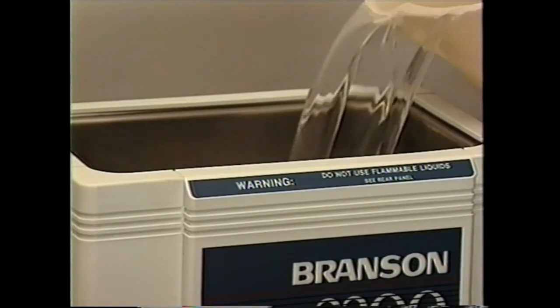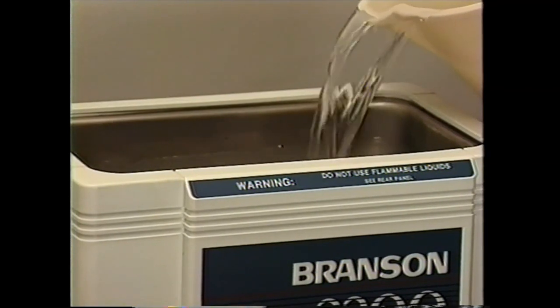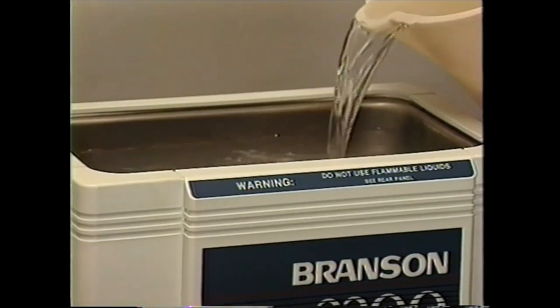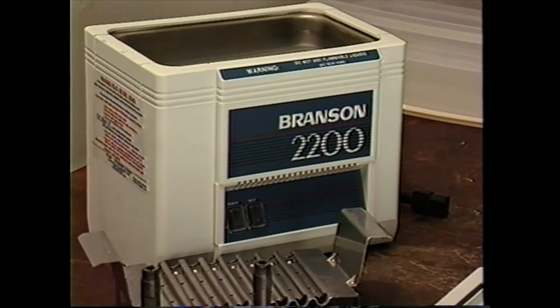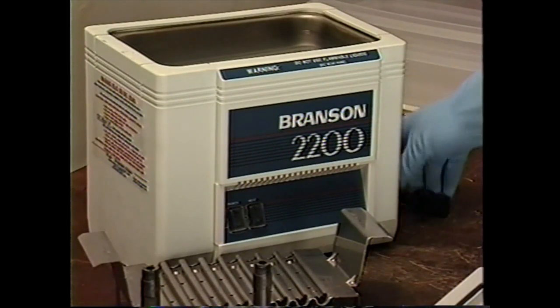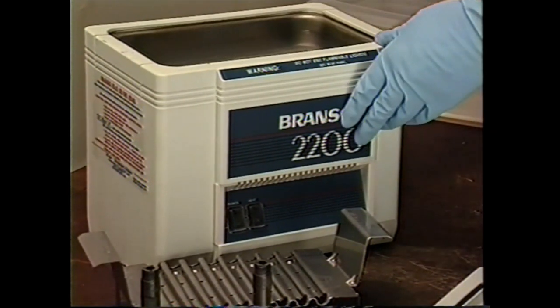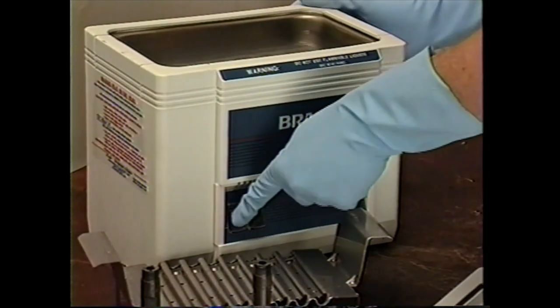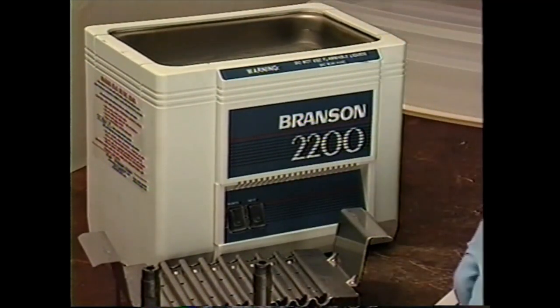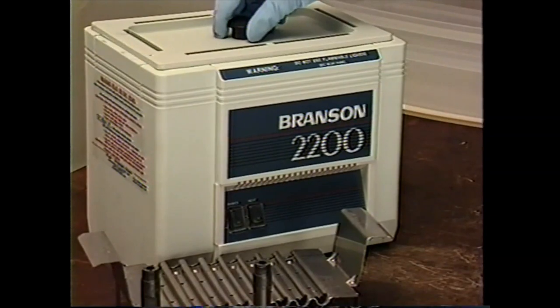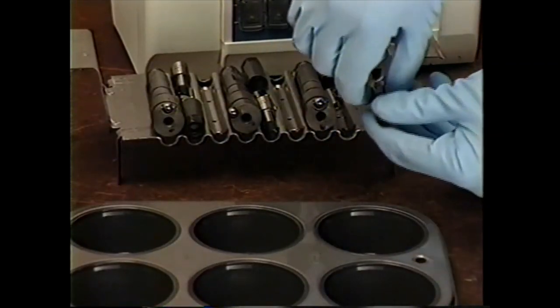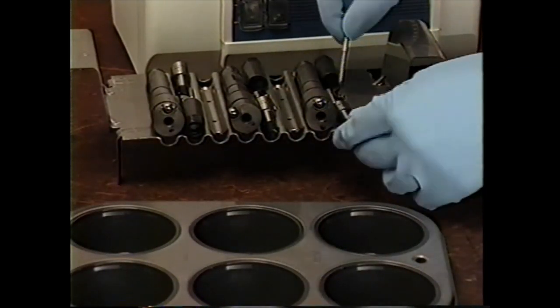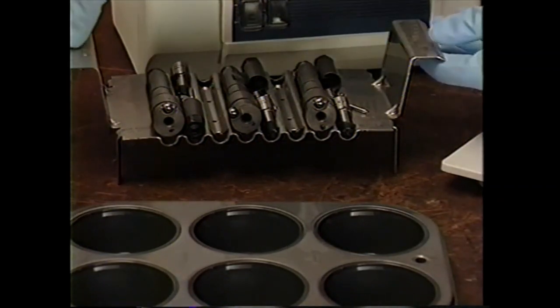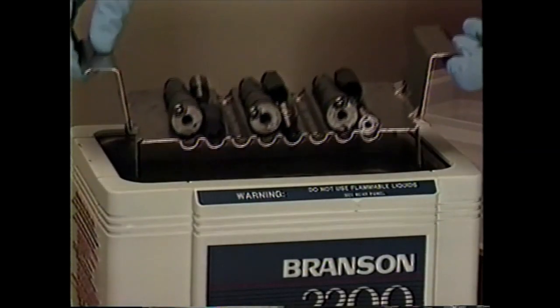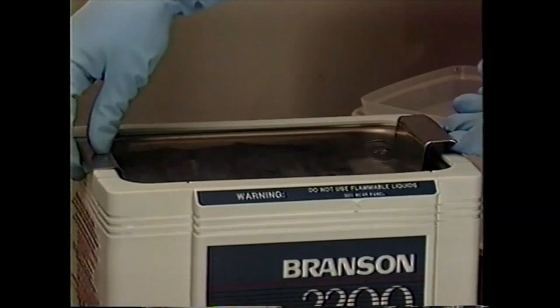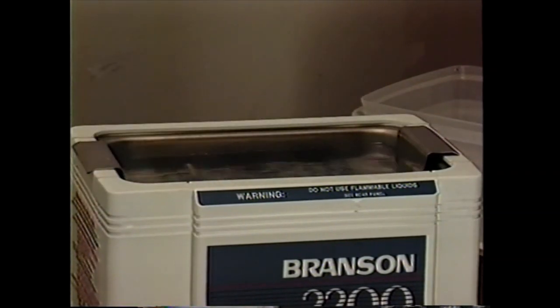Fill the cleaning tank with the solution to within a couple of inches of the top of the tank. Plug the unit in and turn the power and heat on. Allow the cleaner to run for at least 5 minutes so that the cleaning solution can degas. Then position the nozzle parts on the stainless steel holding tray and lower the tray into the tank. Do not place any parts directly on the bottom of the cleaning tank.